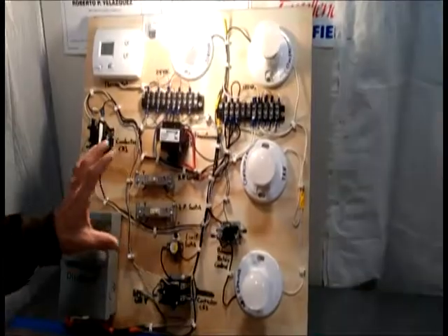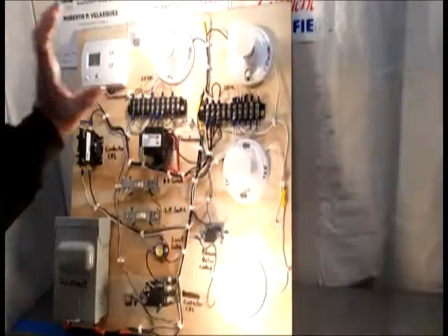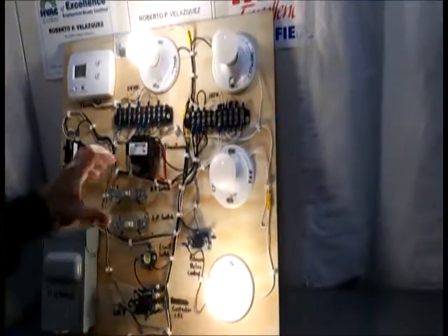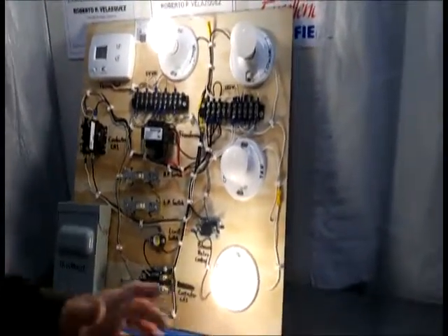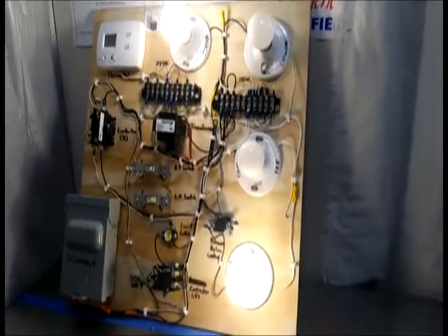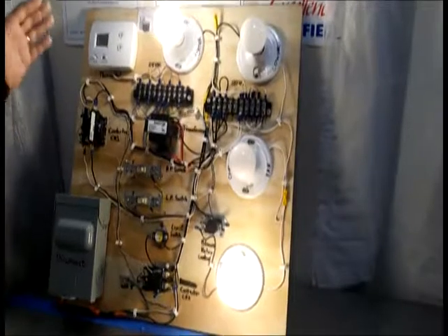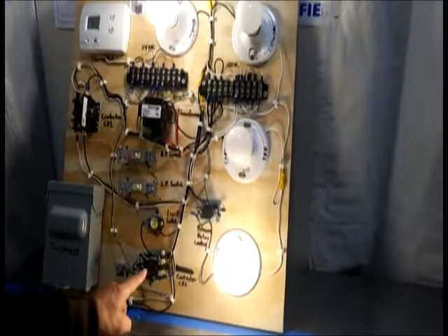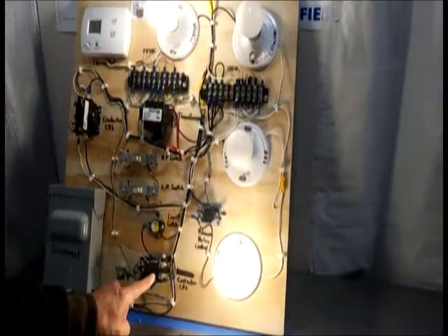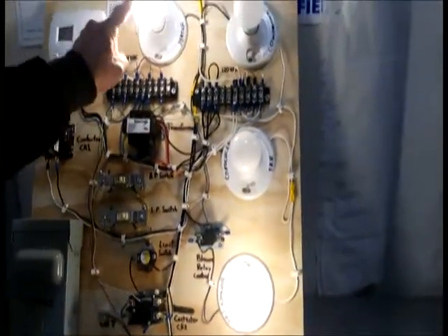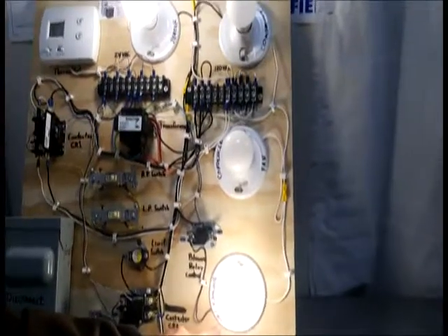Okay. Now we're going to hear a click right there. So the heater element is working. So it starts working, and then after a while, when it is heated up, the blower fan motor starts working and starts heating the house. It starts warming the house, which is good. See, now in the heating mode, the contactor is to activate the heater element right there. So we have the 24 volts in the coil right there. See, and the heater is working and the blower fan motor is on.